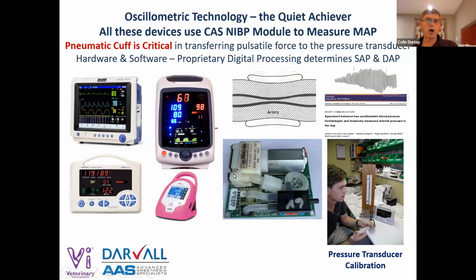We measure blood pressure with all kinds of devices, including oscillometric devices. A whole lot of different devices use the same fundamental technology, and that's a CAS Medical designed blood pressure module from about 1985, and the thing is bomb-proof. And that thing is inside a lot of monitors. You do have to calibrate these monitors. Oscillometric blood pressure is looking for the pulsations in the cuff or the artery at the point that the occlusion is going from fully occluded to release. And these vibrations are only about 2 to 3 millimeters of mercury.